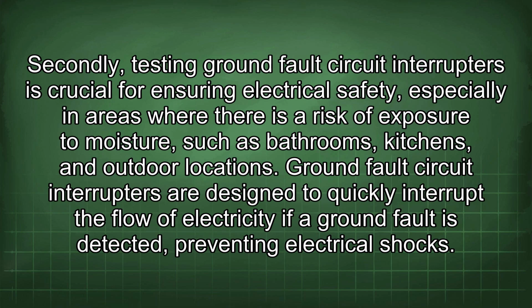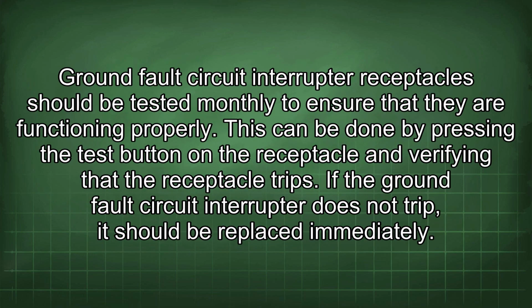Secondly, testing ground fault circuit interrupters is crucial for ensuring electrical safety, especially in areas where there is a risk of exposure to moisture, such as bathrooms, kitchens, and outdoor locations. Ground fault circuit interrupters are designed to quickly interrupt the flow of electricity if a ground fault is detected, preventing electrical shocks. Ground fault circuit interrupter receptacles should be tested monthly to ensure that they are functioning properly. This can be done by pressing the test button on the receptacle and verifying that the receptacle trips. If the ground fault circuit interrupter does not trip, it should be replaced immediately.